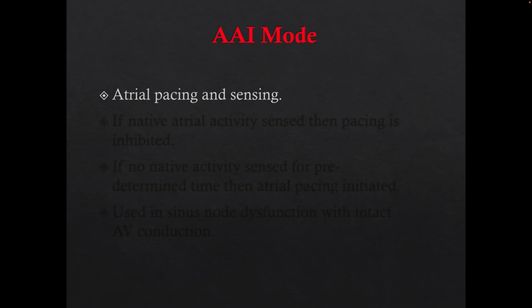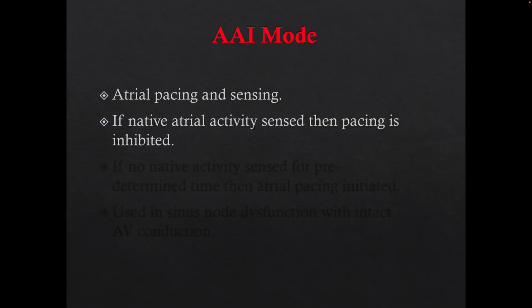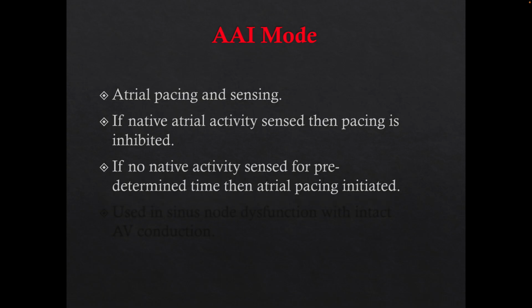So atrial pacing and sensing, right? If there's native or intrinsic atrial activity, it's sensed, then pacing's inhibited, right? Because A is pacing first, second is sensing, and I is inhibiting. So if there's no native activity sensed, then the atrial pacing is initiated. So that means if there is no atrial or P wave, it will pace based on the rate. So if you set it AAI 60 and the rate falls to 50, the device is going to see that and it's going to pace, right?